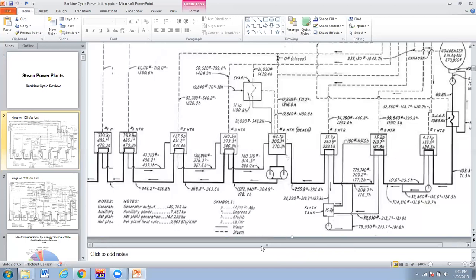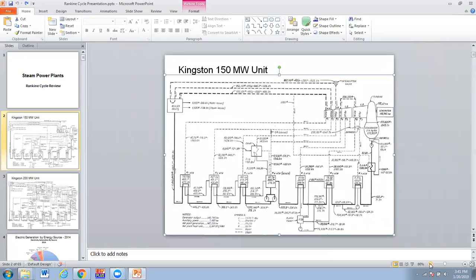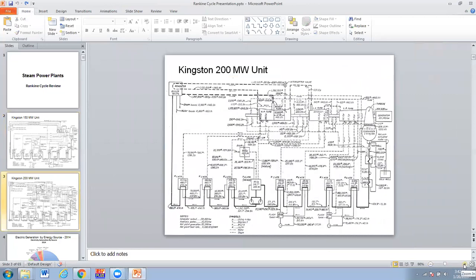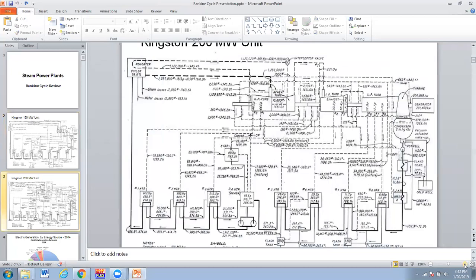That's a good walk around the system for now — we'll go back in much more depth and detail as we progress through the course. Moving on, here is the 200 megawatt unit. It does a lot of the same things but now has eight feed water heaters and a larger cycle. Main steam flow is 1,287,000 pounds per hour. The reheat steam, feed water heaters, and condenser are all present — generally it's just a bit more complex and larger.